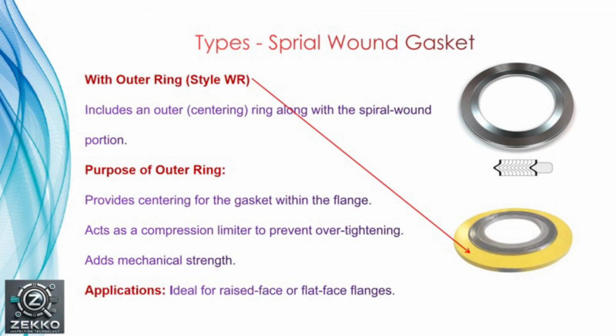The second type of spiral wound gasket is with outer ring. It is also called style WR. It includes an outer ring along with the spiral wound portion. The purpose of the outer ring is to provide centering for the gasket within the flange and act as a compression limiter to prevent over tightening. It adds to the mechanical strength of the gasket. Basically, in application, it is ideal for raised face and flat face flanges.